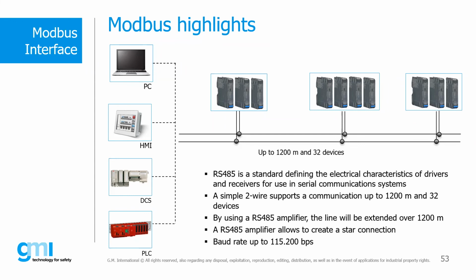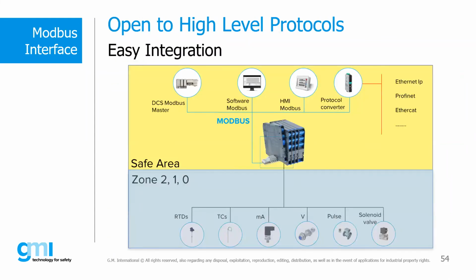A slave doesn't send any message before the master requests it, as there can be several devices connected on the same RS485 bus, so each slave must use a unique ID on the bus. But what are the advantages of using Modbus communication? Well, with a single Modbus RS485 interface, it's possible to connect and communicate with all the devices present on the same bus. Multi-drop connection is possible, and communication can cover a distance of up to 1,200 meters. And another advantage is the possibility of not using a dedicated digital input system to monitor alarms. This allows us to have a significant saving in terms of cost.